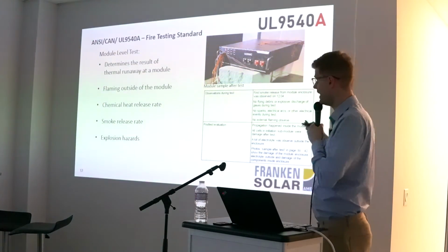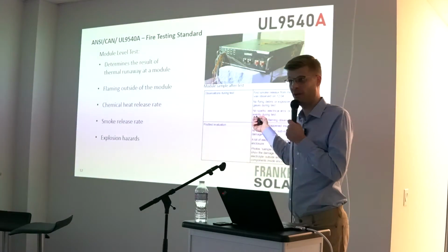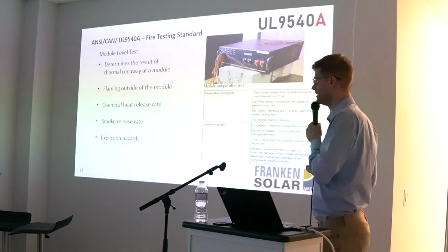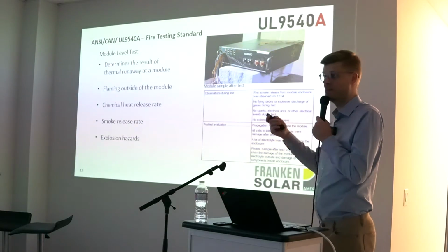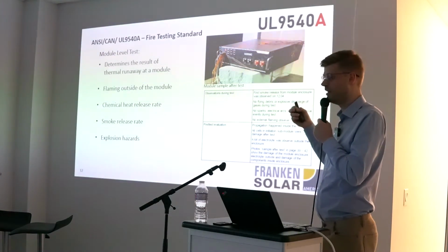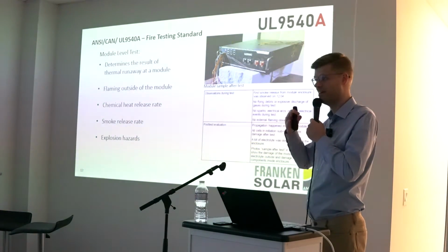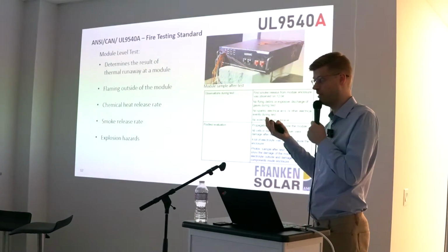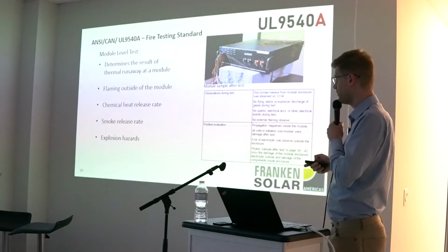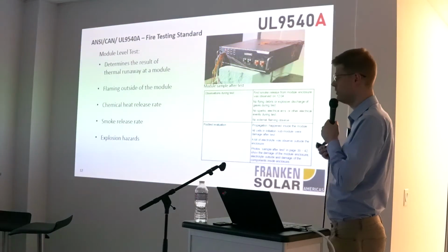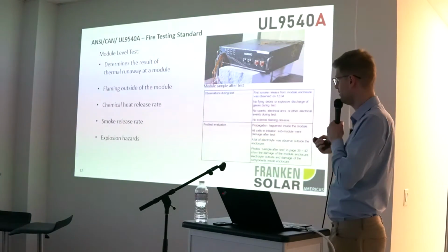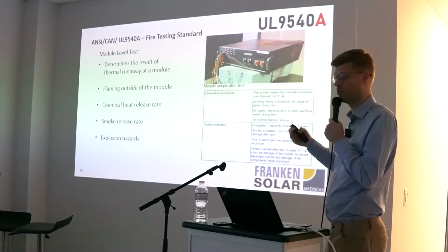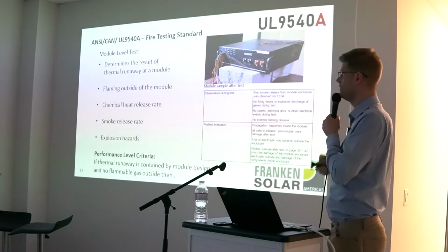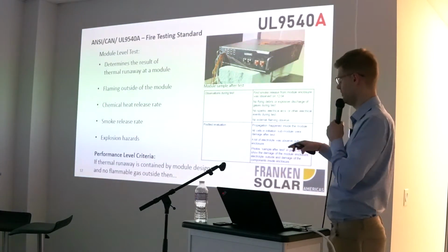But what if you have a chemistry that is maybe not a lithium iron phosphate like this manufacturer here, and you have an NMC that has a significantly higher heat release rate and thermal runaway from an energy perspective? You have to do probably a little bit more, and maybe your module will actually have some exposure, or flames are coming out. Then you need to go into the next level.